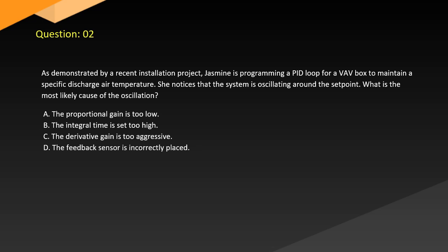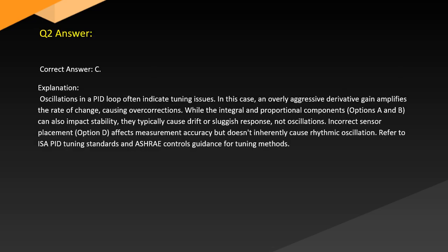C. The derivative gain is too aggressive. D. The feedback sensor is incorrectly placed. Answer. Correct answer: C. Explanation. Oscillations in a PID loop often indicate tuning issues.